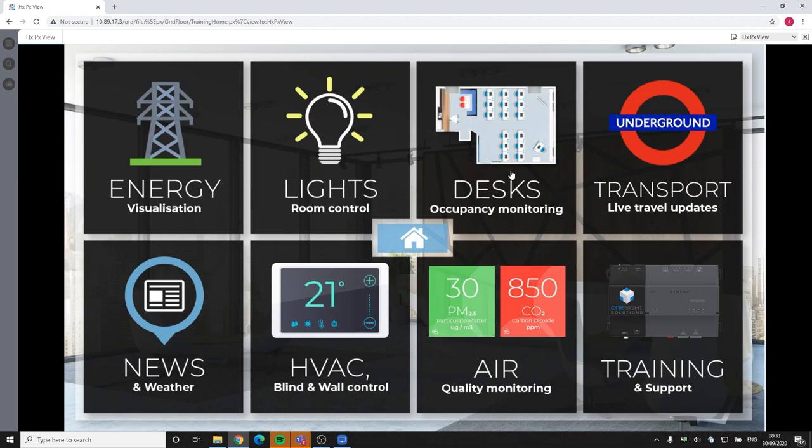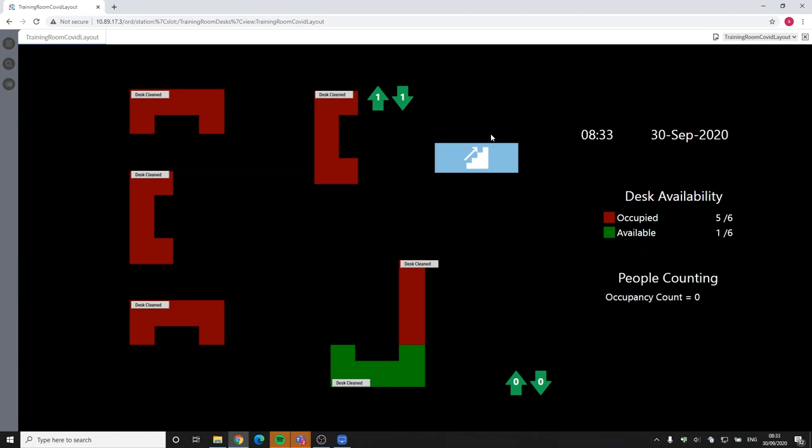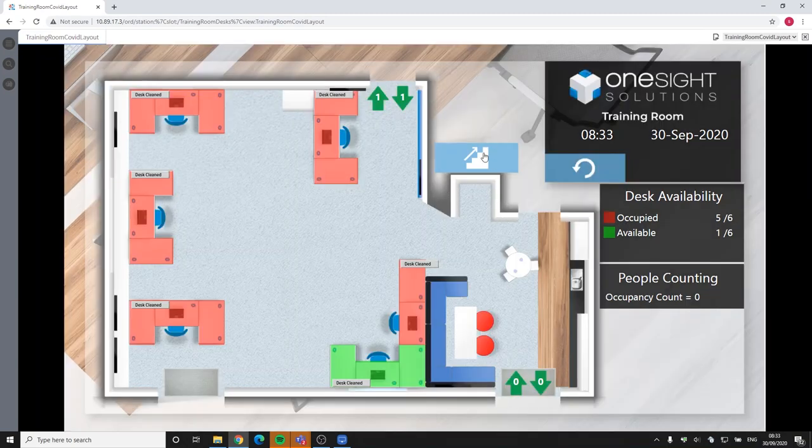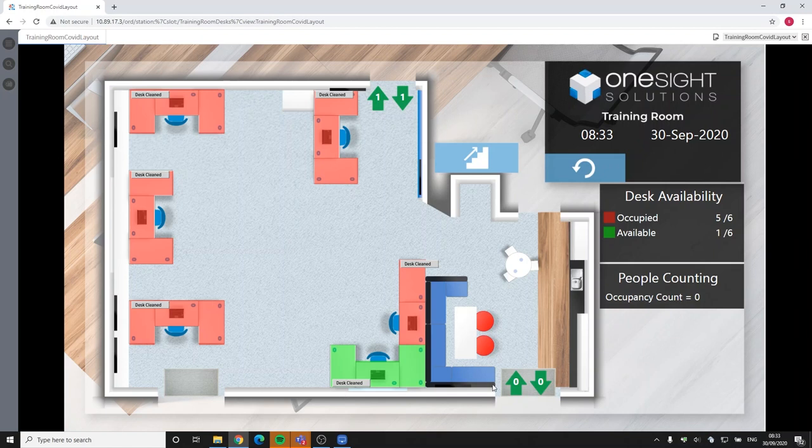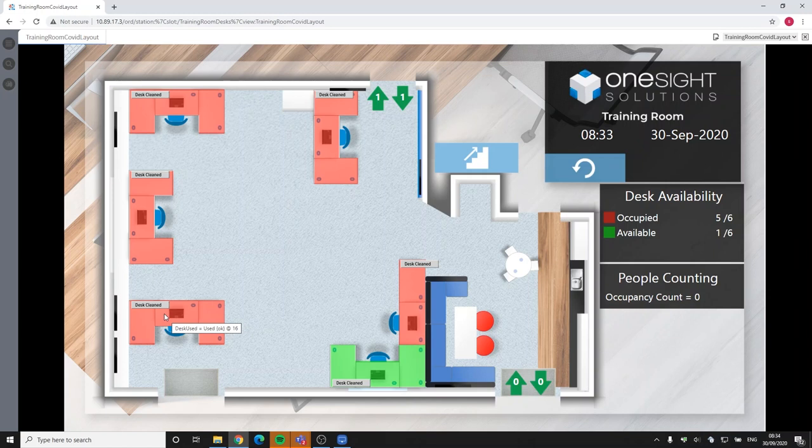So firstly I'm going to click through into the Niagara 4 supervisor and I'm going to go to our desks. And as you can see here, this is one of the rooms within the office and we have sensors underneath each of our desks. Now these sensors are of different technologies. Some are using LoRaWAN, some are using PRESSAC and others are using EnOcean.